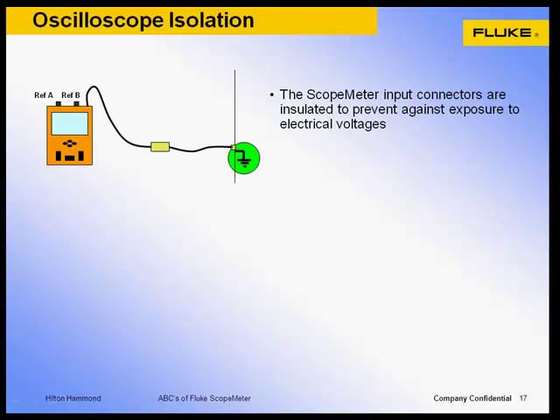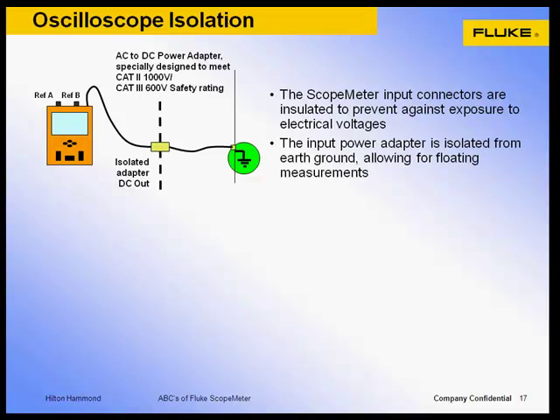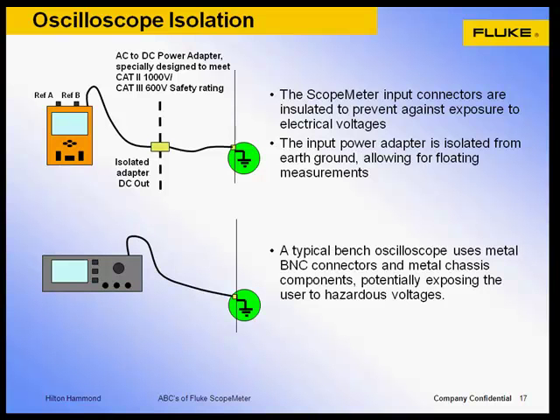The Fluke Scope Meter test tool includes insulated BNC input connectors and isolated power adapters that provide a safe means to float the oscilloscope input above earth ground. Both input channel A reference and channel B references are isolated from earth ground. On some Fluke Scope Meter models, like the 190C series or 220 series, the input A reference and input B reference are also electrically isolated from each other, making it possible to perform differential measurements without the need for an external differential amplifier or specialized accessory.